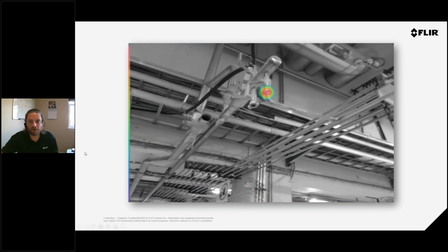So the great thing about using this camera is it's very easy to use, one-handed use. All you have to do is trace, in your facility, from your compressor all the way through where air can be going. You're going to have different hoses and whatnot, and see if there's any activity. And if you get an image like this at a connection, you have a bad connection right there. You can take that image, save that image, and then continue on to try and find more. These images go up to the cloud, and then they can be saved there. And then you can come back to this spot after you send somebody out to go fix it. You can come back and scan it again. And hopefully, after somebody went and fixed it, you're not going to see this image, this target showing you that air is still coming out.